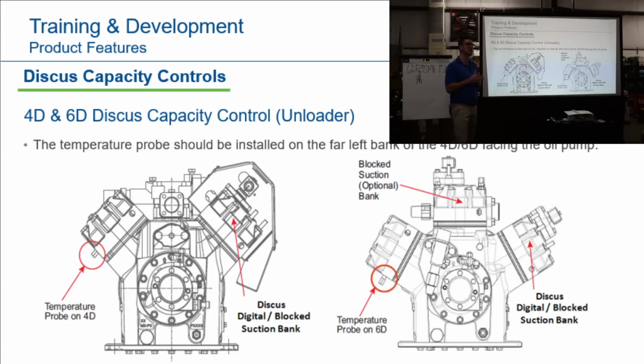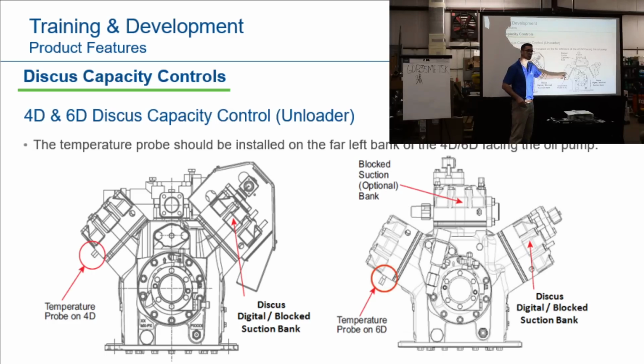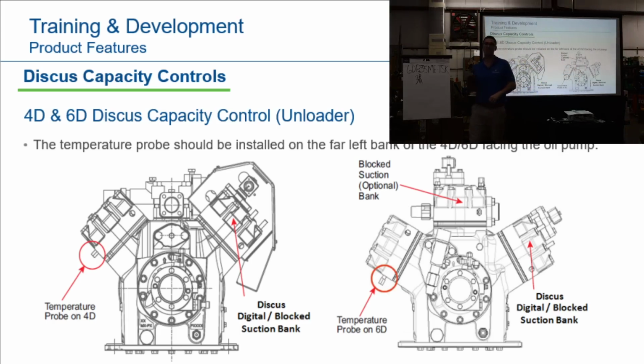Okay. This is a really important slide if you work on semi-hermetics. When you're looking at the pump, the temperature probe always has to go into the left side. Once again, where would I find this picture? Bulletin? Application engineering bulletins. Block suction or digital discus will go on this side. 6D, same thing. You're looking at the pump side, the temperature probe goes in it, because this one's always running. This is your 33%. This one here could be a block suction optional or a digital or discus on the right side. Everybody follow me there? Okay.